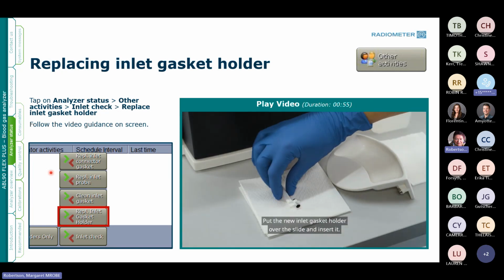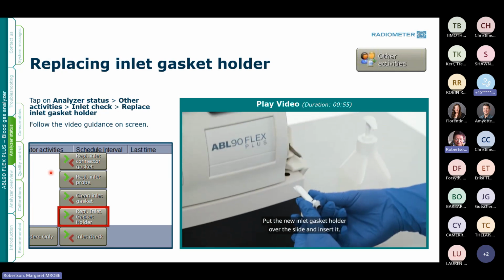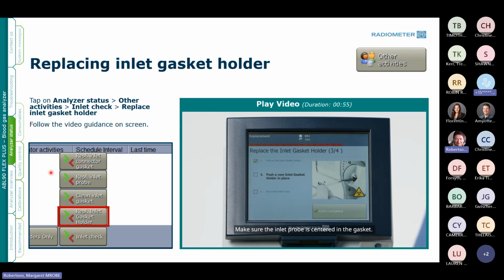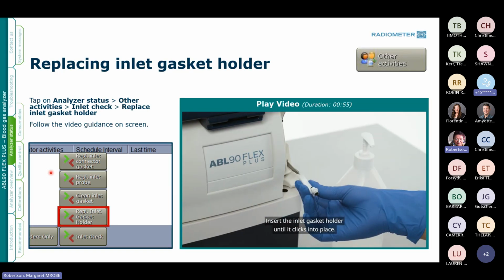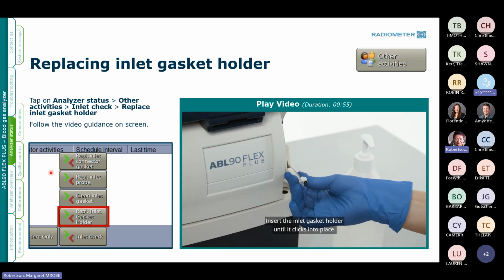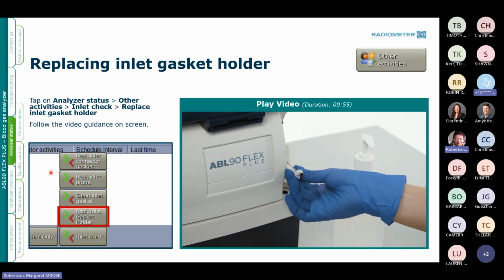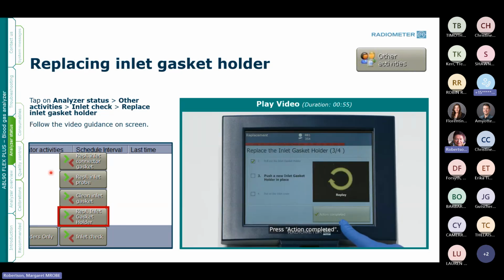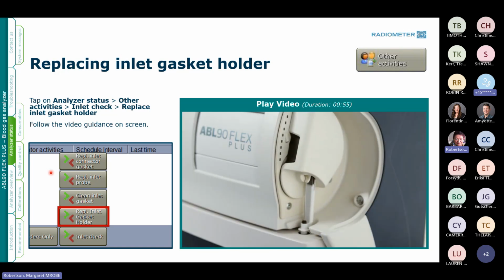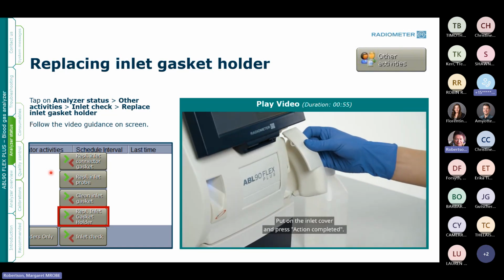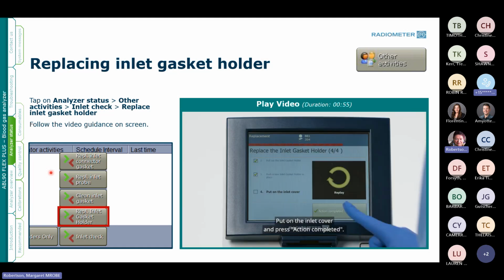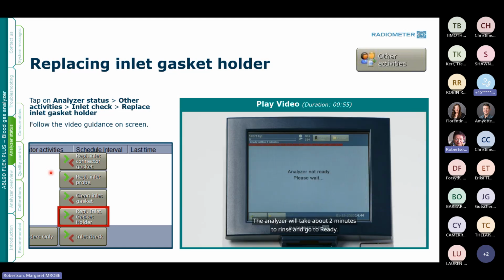Put the new inlet gasket holder over the slide and insert it. Make sure the inlet probe is centered in the gasket. Insert the inlet gasket holder until it clicks into place. Press Action Completed. The analyzer will close the inlet. Put on the inlet cover and press Action Completed. The analyzer will take about 2 minutes to rinse and go to Ready.